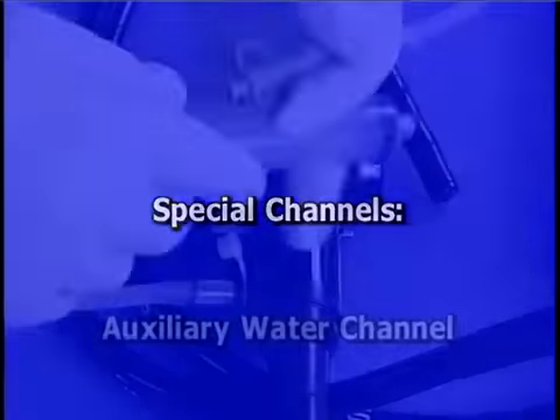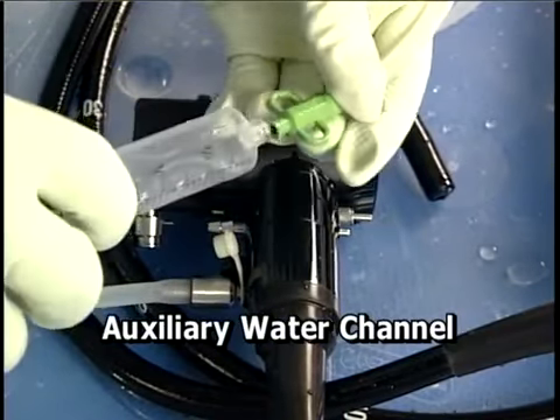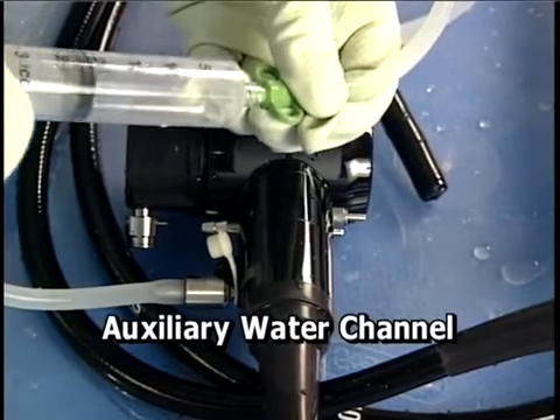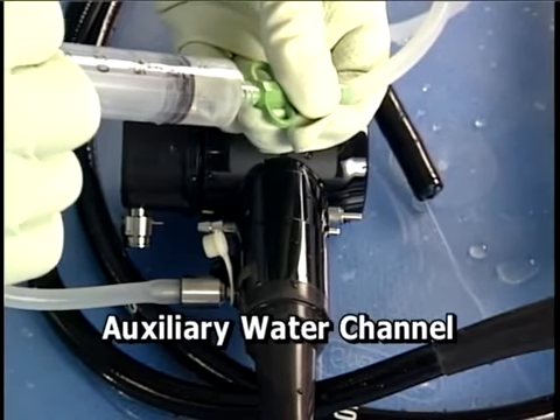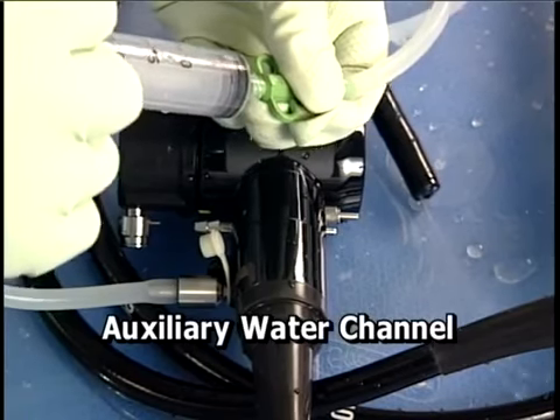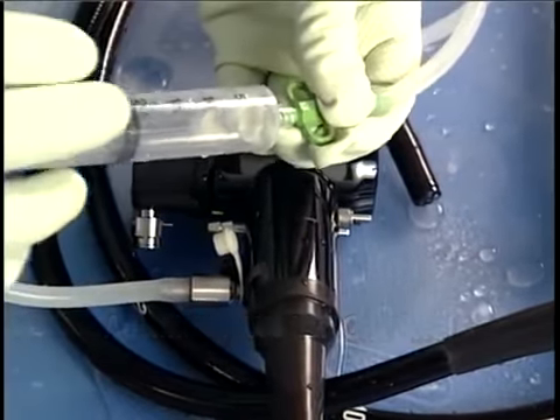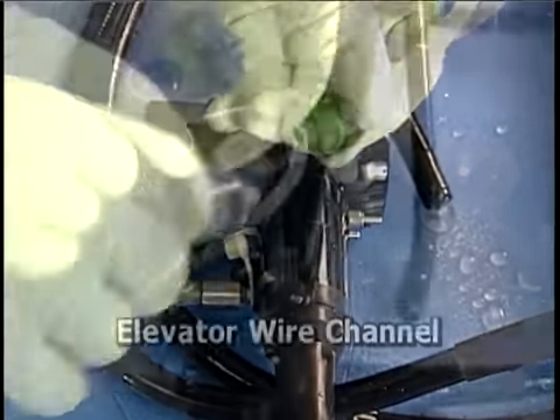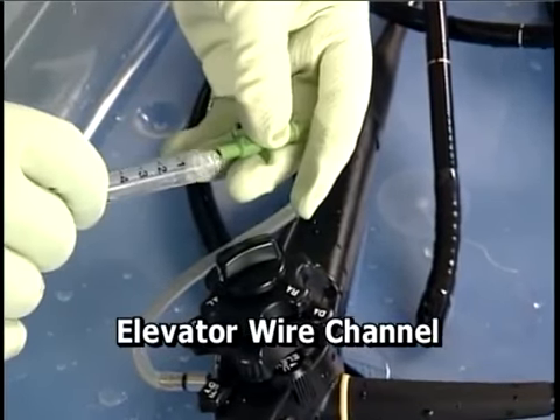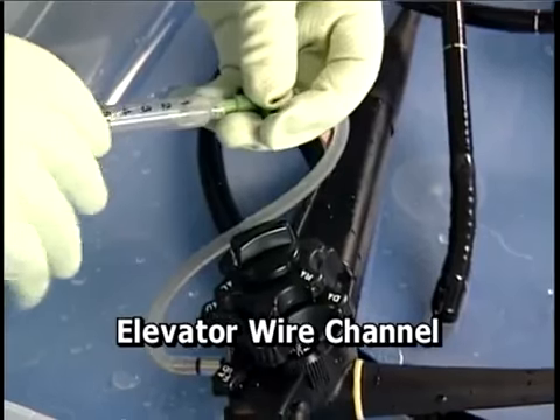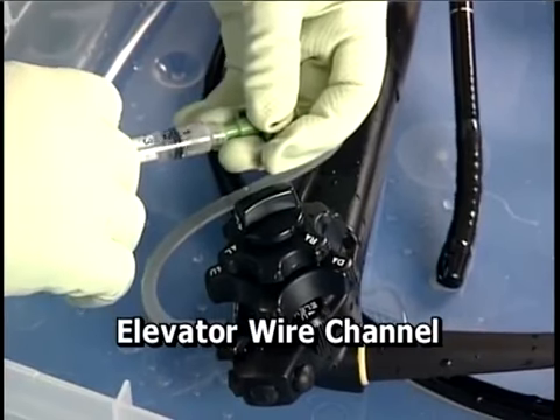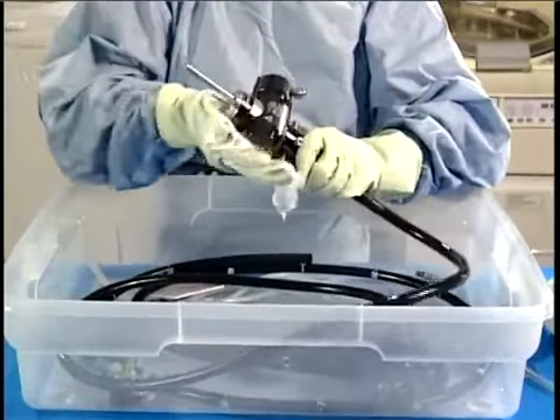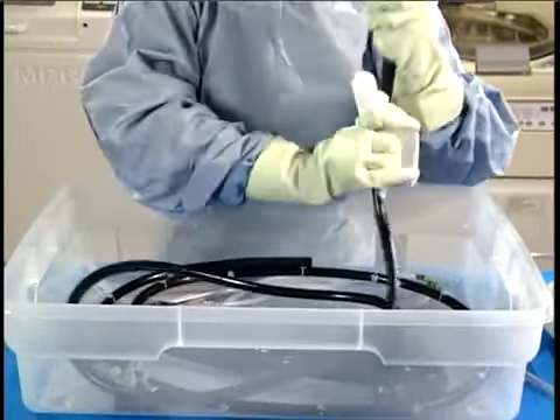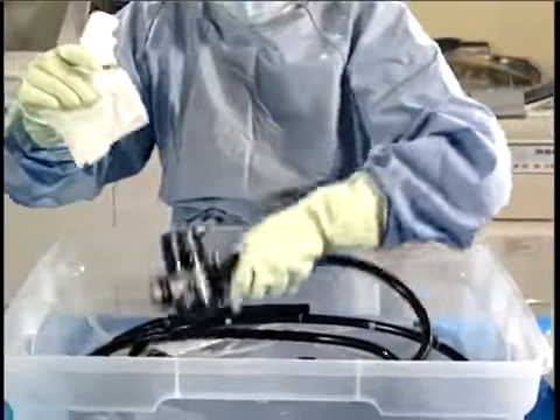If you are reprocessing an endoscope with a special channel, use a syringe to inject air into the auxiliary water channel. If you are reprocessing a duodenoscope, inject air into the elevator wire channel in order to expel rinse water from this channel as well. Use a sterile lint-free cloth to thoroughly dry the external surfaces of the endoscope and reprocessing accessories.